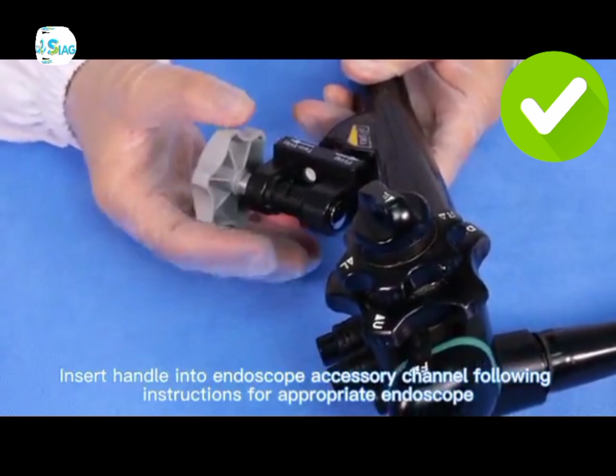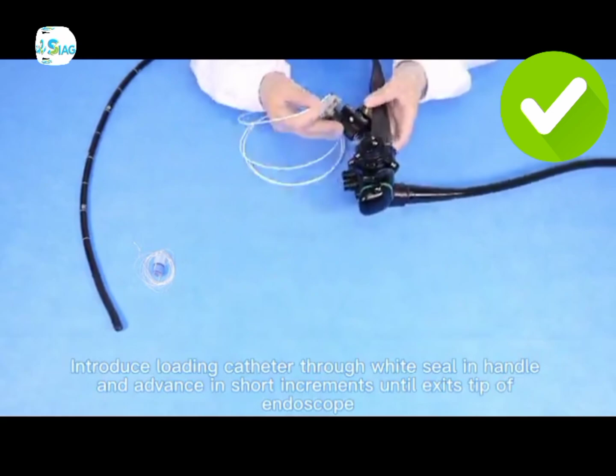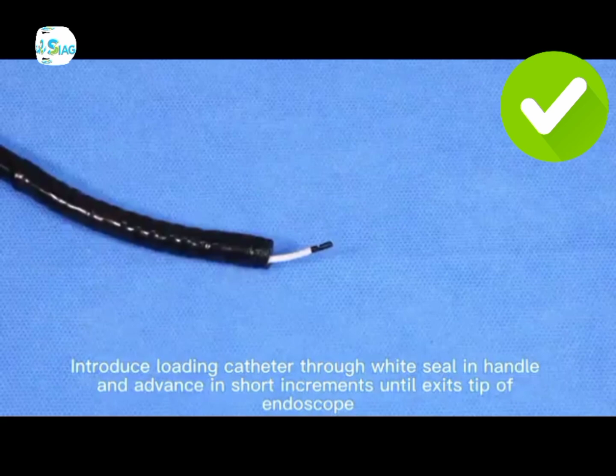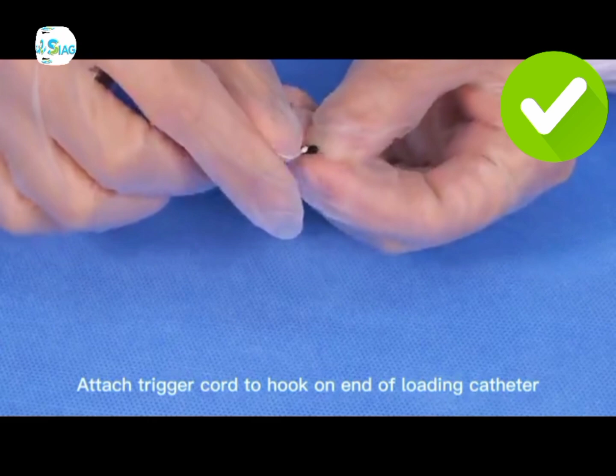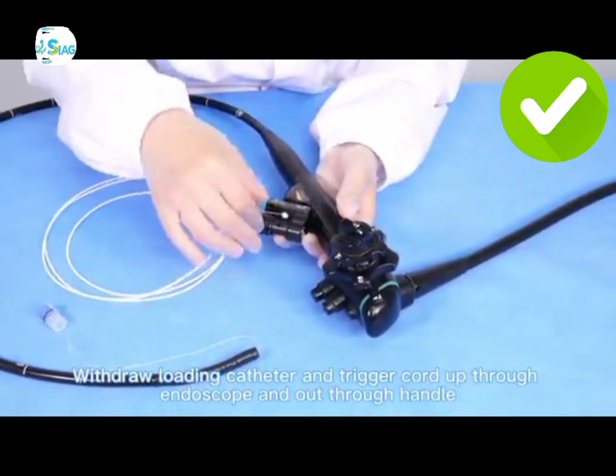Second, insert the handle into the endoscope accessory channel, following instructions for the appropriate endoscope. Third, introduce the loading catheter through the white seal in handle and advance in short increments until it exits the tip of the endoscope. Fourth, attach the trigger cord to the hook on the end of the loading catheter. Withdraw the loading catheter and trigger cord up through the endoscope and out through the handle.